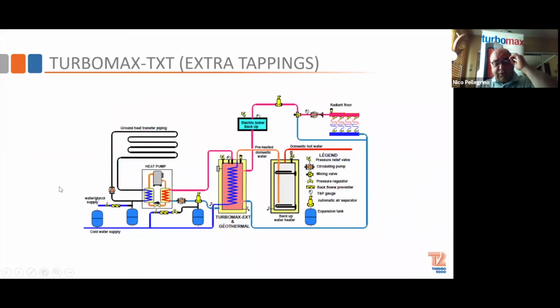So this is just showing a Turbomax with the extra tappings married to a geothermal system. Obviously, because geo has a limited temperature, you have to bring up the temperature for in-floor if you're doing high temp, and also you need a finishing tank for your domestic water so that you can get it up to the temperature that you need.